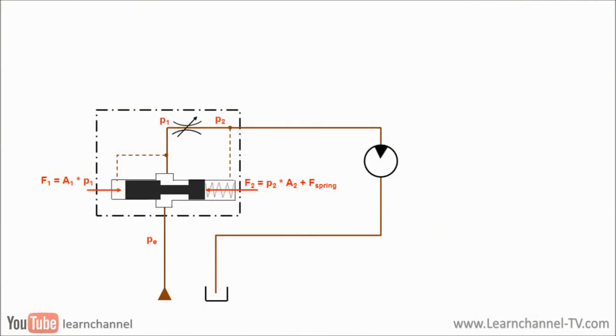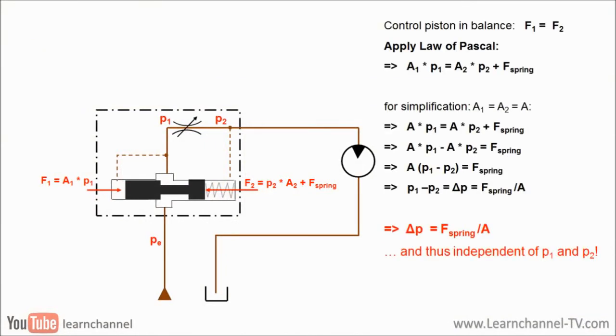Consider the control piston in balance. As deduced aside, the pressure drop at the throttle point is independent of pressure P1 or P2, but of constant value. However, this also means that the flow rate must be constant.